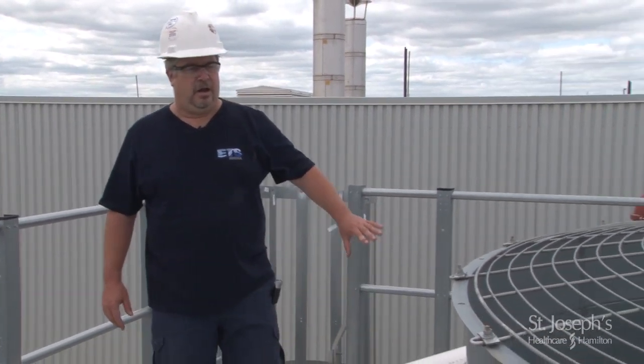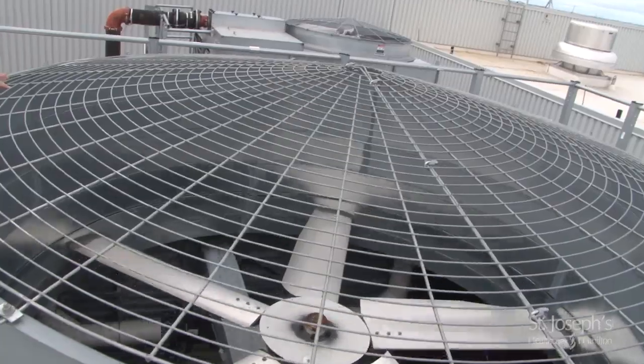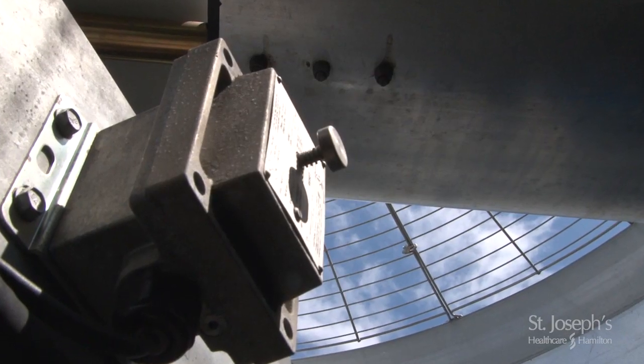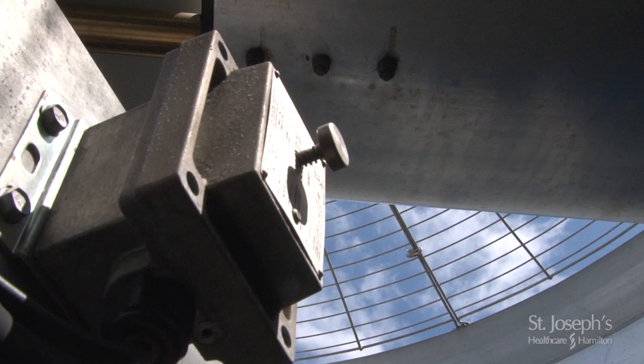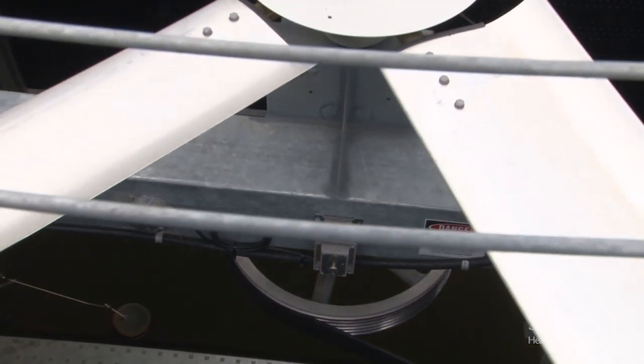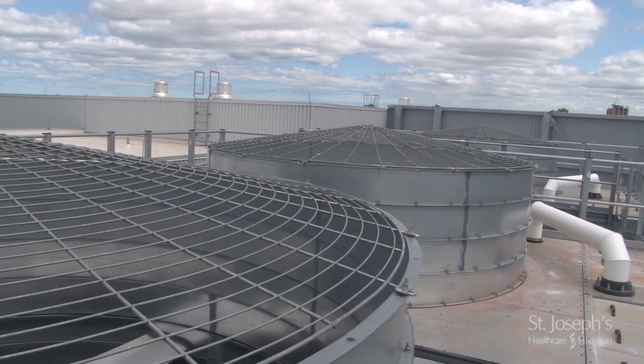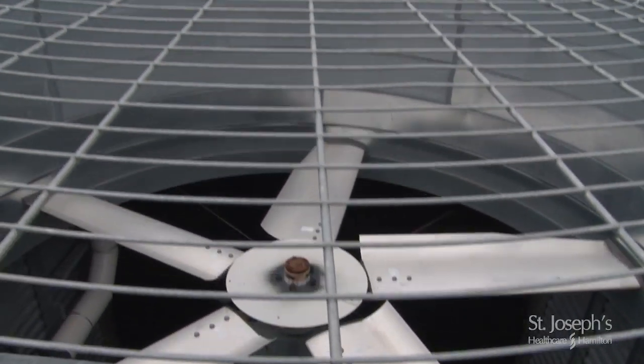On a semi-annual basis, or twice a year, we should be opening up these boxes and just cleaning them out. Usually a shop vac is sufficient to clean that dirt out of there, and it allows for a good even flow across your entire fill media to ensure proper efficiency of the cooling tower. Over here you'll see our top view of our fan assembly. Just looking down, you can get a really good shot of that vibration switch we were speaking of earlier. If you ever need to do some major service on the actual fan assembly itself, this is how we would access the fan. We would take off this screening, and the fan would just pull out right through the top of the cooling tower. We do our maintenance and then reassemble everything back through the top.